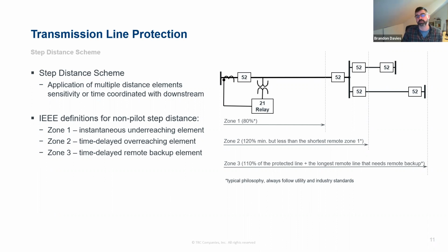So I guess to answer your question, it's certainly something that needs to be considered in the design of the relays, and it needs to be understood how it's going to operate. But it's not something we need to build into our calculations for the set points, but would be more likely to be something that would be flushed out when we do the set points, we do the calculations, and then we model it in Aspen or another fault modeling program, and run a bunch of faults to see how it responds. That should tell us how it's going to react to those different scenarios for in section or out of section faults.